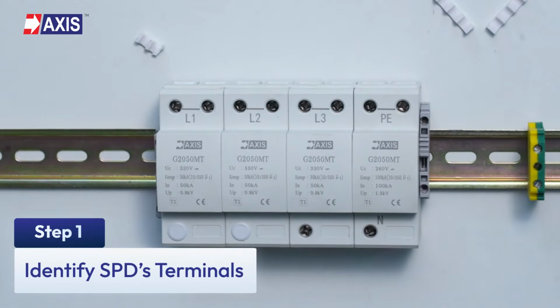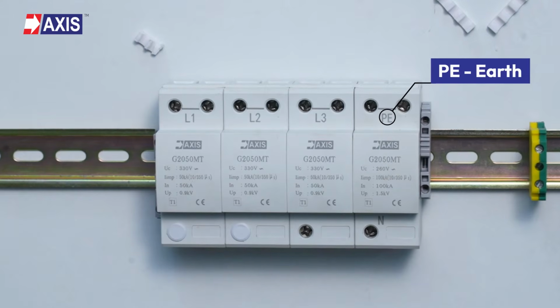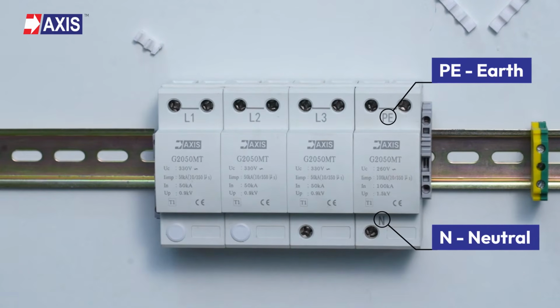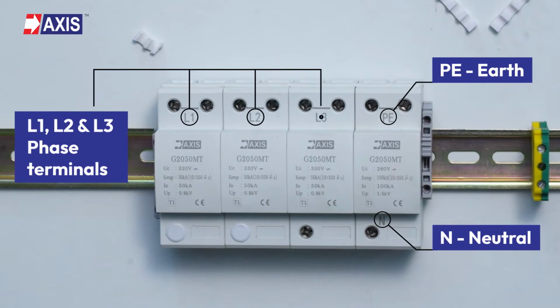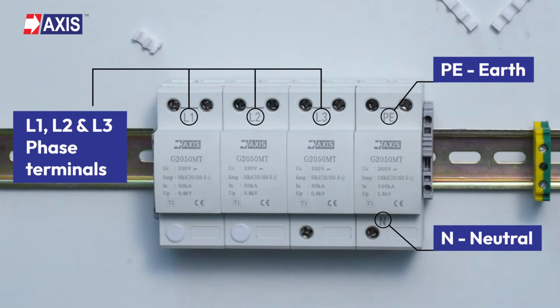Step 1. Identify the SPD's terminals. As you can see, the terminal marked PE is for earth, the terminal marked N is for neutral. Phase terminals are marked L1, L2 and L3 respectively.